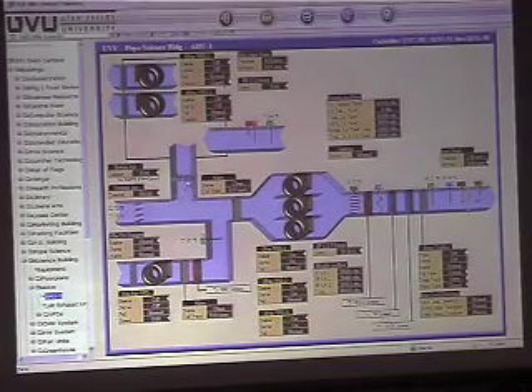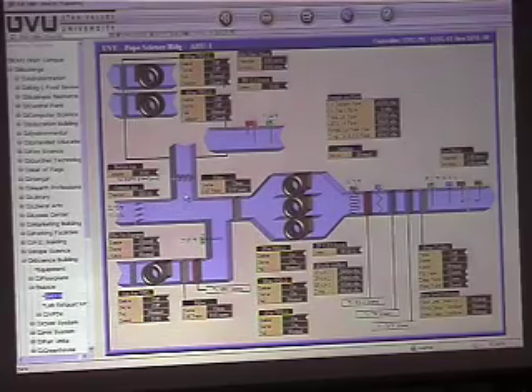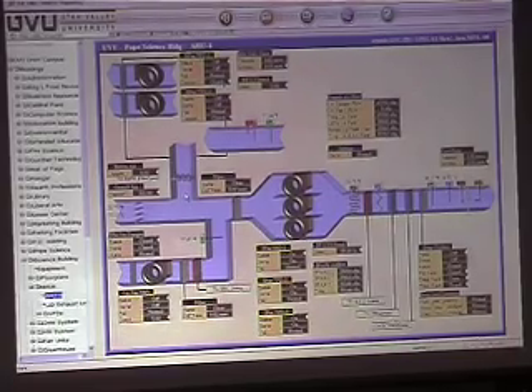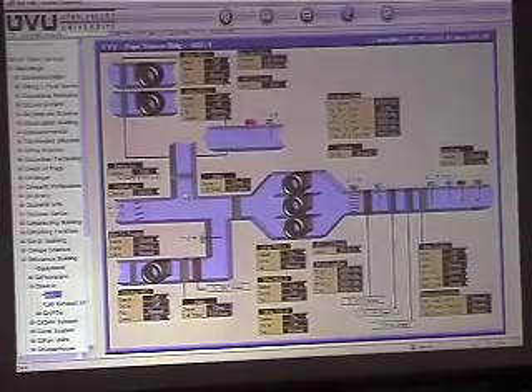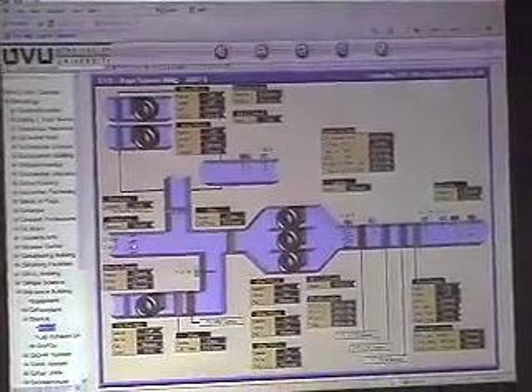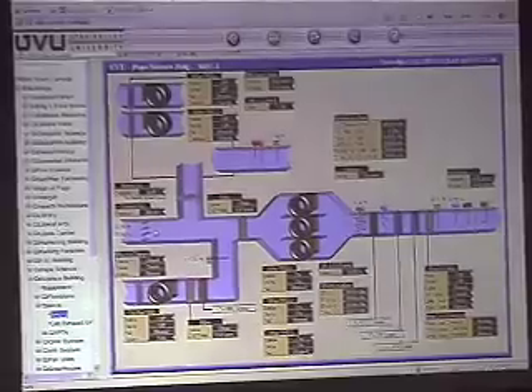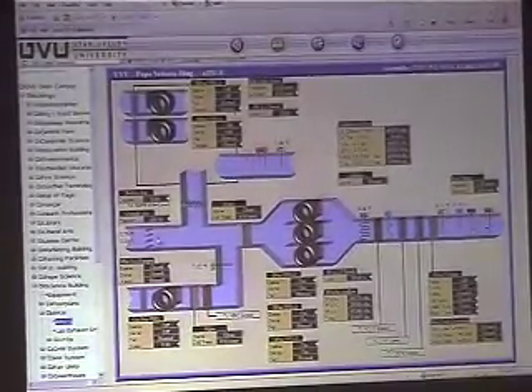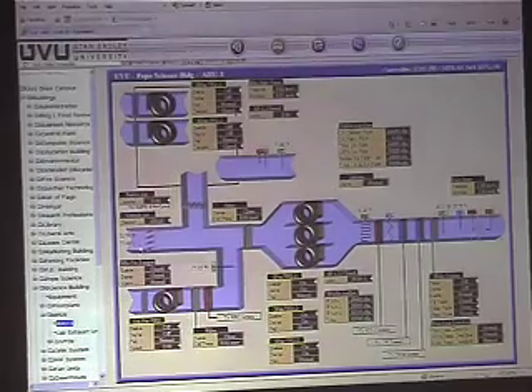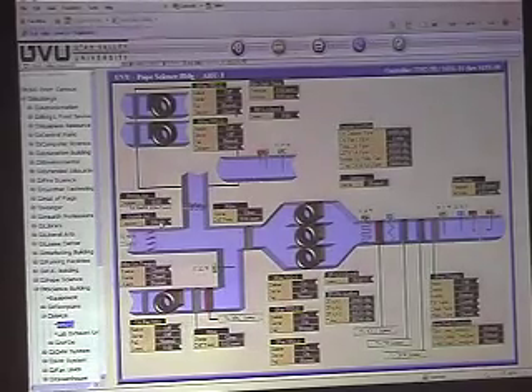In your economizer section, this air handler operates a bit differently than you would typically see. The outside air damper actually operates off of flow, so it's maintaining enough airflow to make up what the lab exhaust fans are exhausting, bringing in enough outside air to keep your building positive. So it's allowed to cut back if it's satisfying airflow, but from what I've been seeing so far, a lot of the times this thing's going to be wide open unless it's super cold outside.